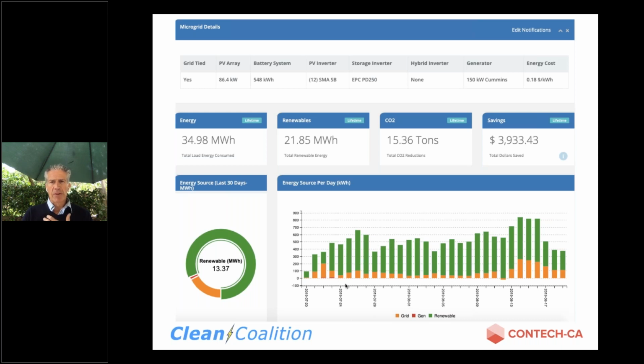So just one thing for the electrical engineers out there, which I honestly hadn't realized the benefit of in this configuration. The reason we have the diesel generator is it was already on site and it's actually recently been replaced. However, one of the problems with a generator is testing, and every month when you test it, you need to have a minimum of 30% load. Oftentimes that's quite difficult to achieve. If you don't get that 30%, you get something called wet stacking, and generators can fail to start if you don't properly maintain them, and you need to add load banks.